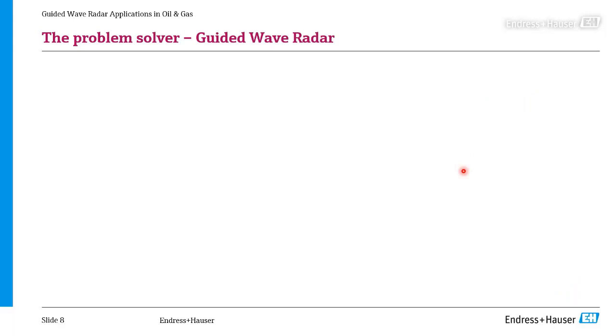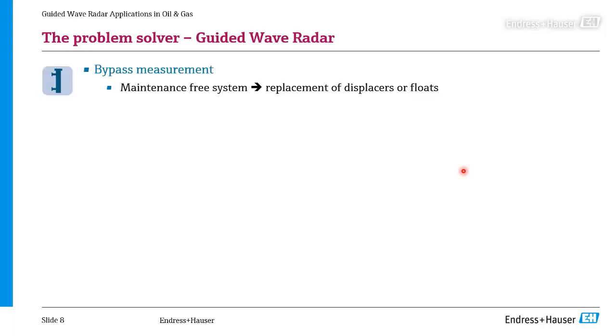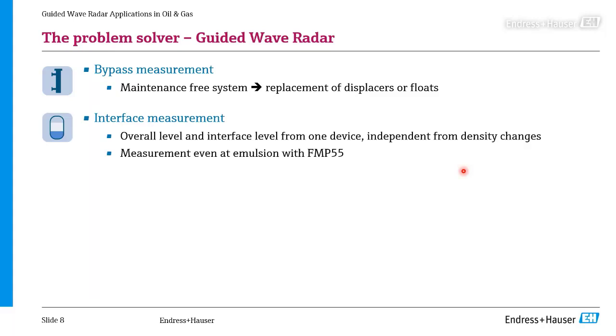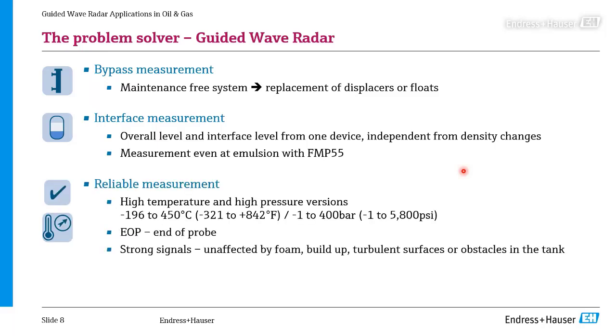Now let's come to our actual topic today, which is guided wave radar. We call it the problem solver, as I already said, especially in the oil and gas industry. And why? Whenever there are bypass measurements, and we see them a lot in a couple of industries, we typically recommend guided wave radar. Whenever you want to measure an interface and you also want to measure the top level, for example, in a separator, you have the interface between water and oil, and you also want to measure the top level at the same time. This can only be done with guided wave radar or maybe with radiometrics, nucleonics, but guided wave radar is maybe the easier version to go to. We have reliable measurements, so we can go to high temperatures, high pressures, but also low temperatures, as you can see.